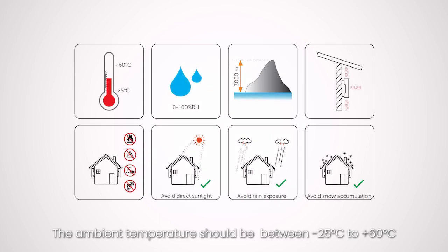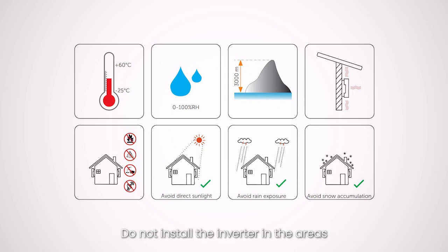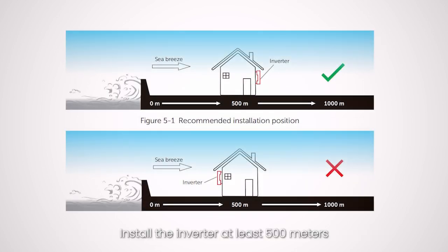The ambient temperature should be between -25 degrees to 60 degrees. The relative humidity shall be between 0 to 100%. Please do not install the inverter in the areas where the altitude exceeds 3000 m, and remember, avoid direct sunlight, rain exposure, and snow accumulation. Install the inverter at least 500 meters away from the coast and avoid sea breeze directly hit.